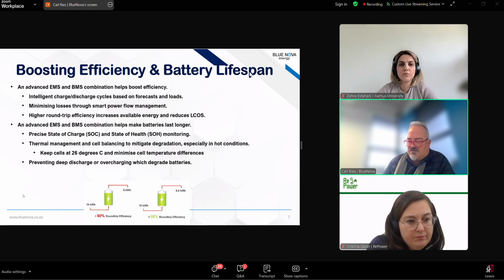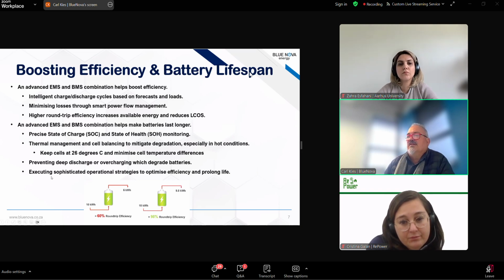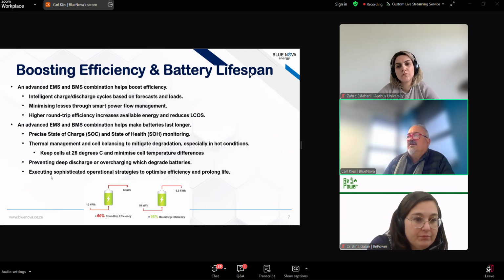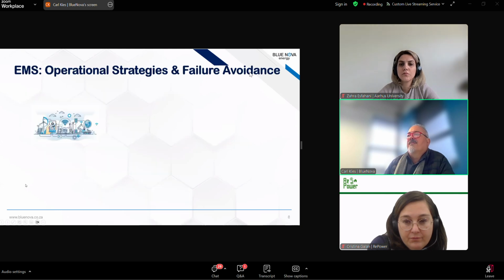For those of you that still use lead acid, you will know if you discharge deeper than 50%, you accelerate the degradation quite rapidly. So this EMS-BMS combination allows you to look at sophisticated operational strategies that can optimize the efficiency and the life of the system.